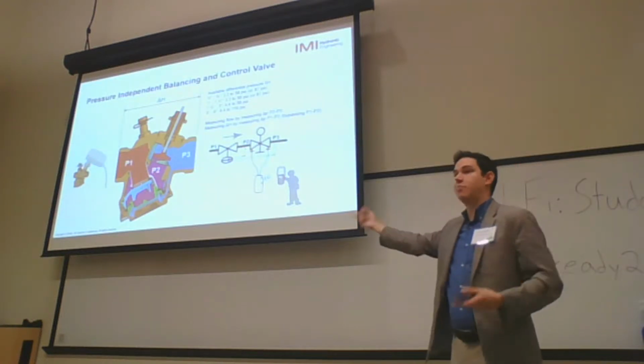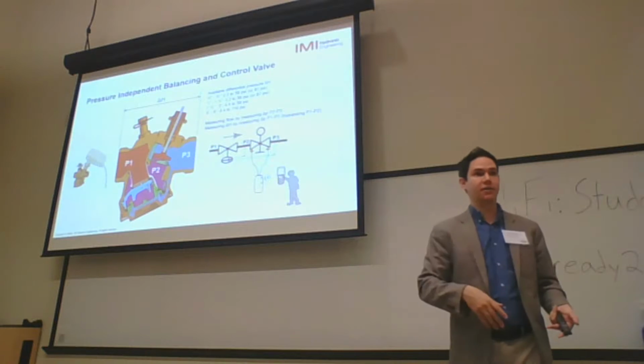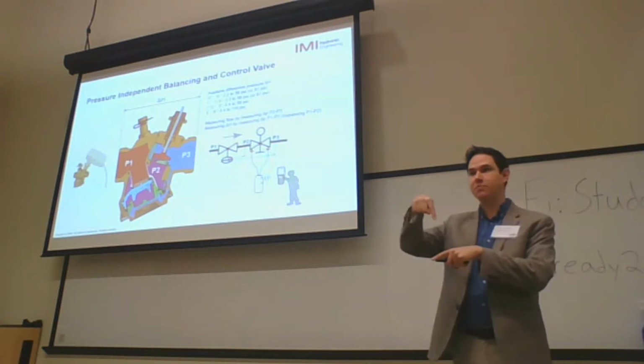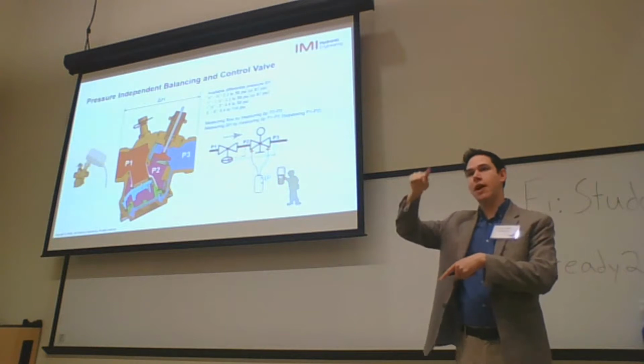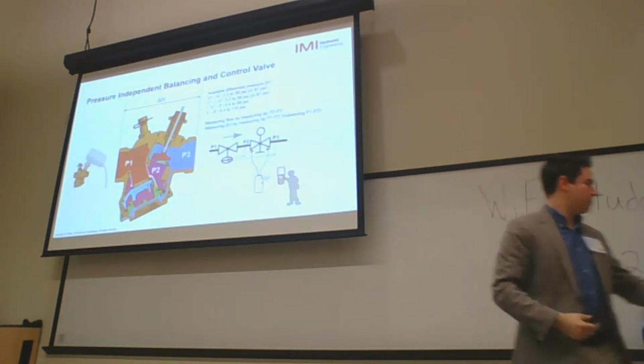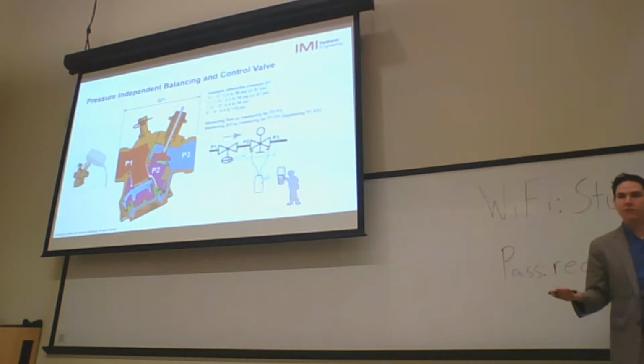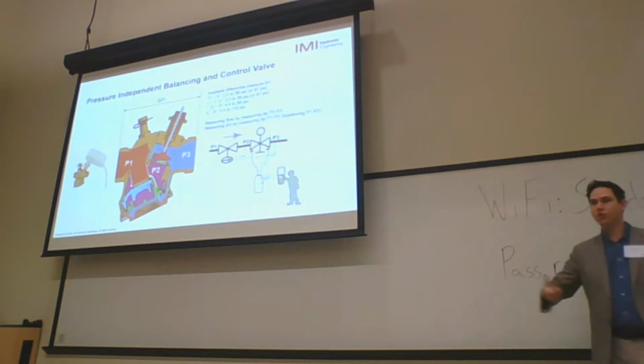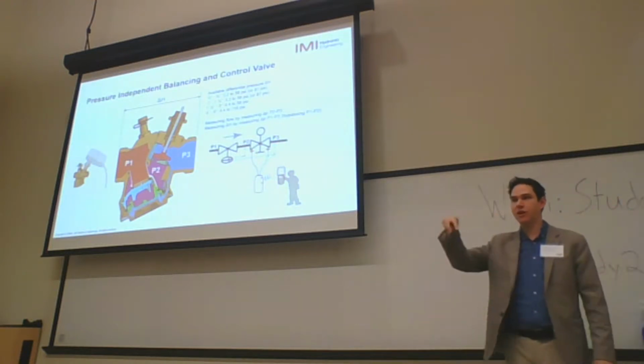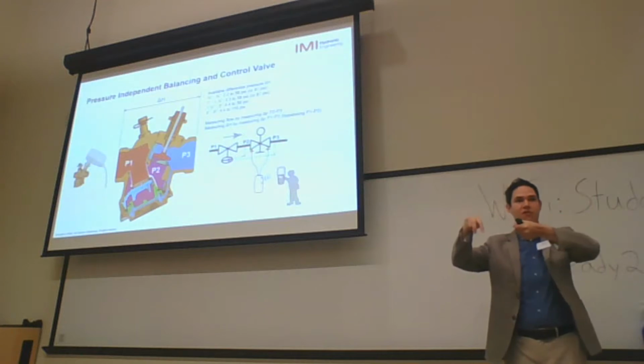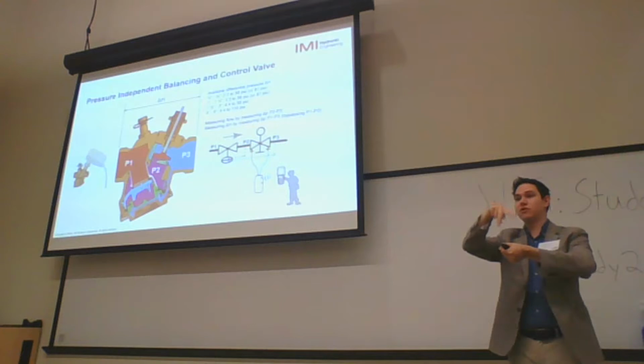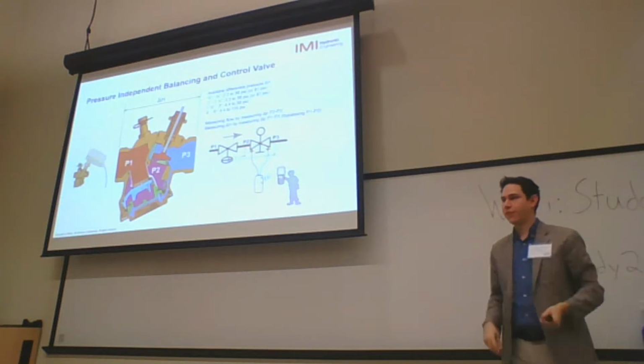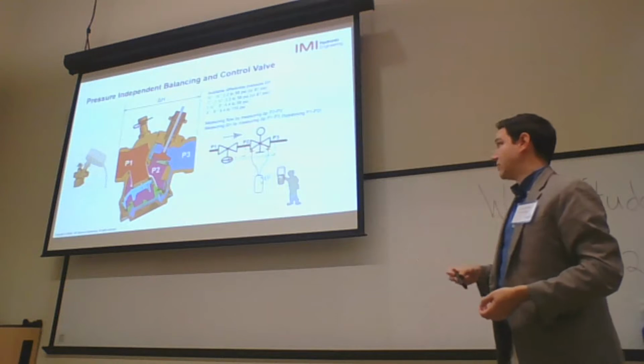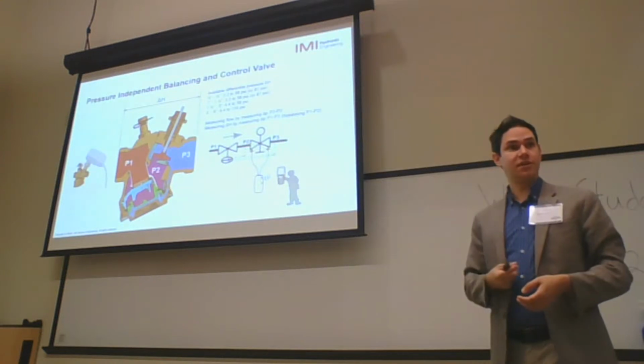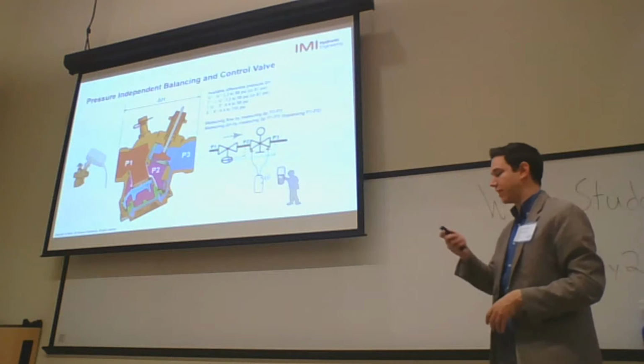And this is the only pressure independent control valve in the market where you can measure available pressure, because you have this PT port function that you can open and bypass the DP controller. Most manual balancing valves can do that because you have the PT ports across the seat. Only a Venturi balancing valve cannot, because with the Venturi, the PT ports are not across the seat. It's not across the valve. But yes, measuring the delta H or available pressure is always a great thing to do as a troubleshooting capability.